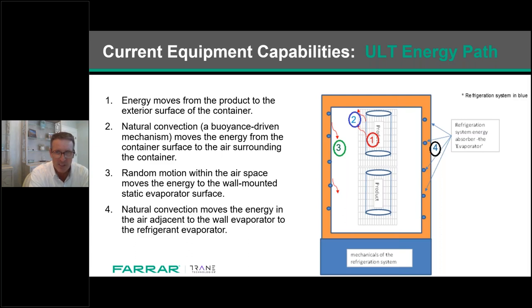On number one, depicted with the red circle, you see that we move the energy from the product to the exterior surface of the container. And then two, we call it the natural convection, moves the energy from the container to the surrounding air. And then three, in the green circle, this is where the random motion or diffusion and buoyancy moves the energy across the space. And then four is the natural convection of the cold wall, which moves the energy into the refrigeration system. So this is how a ULT freezer is designed to move the energy. Next slide, please.